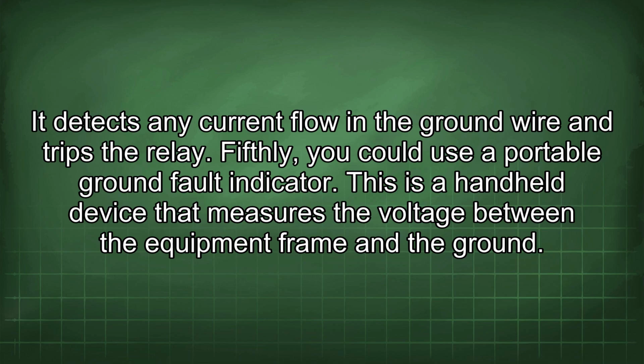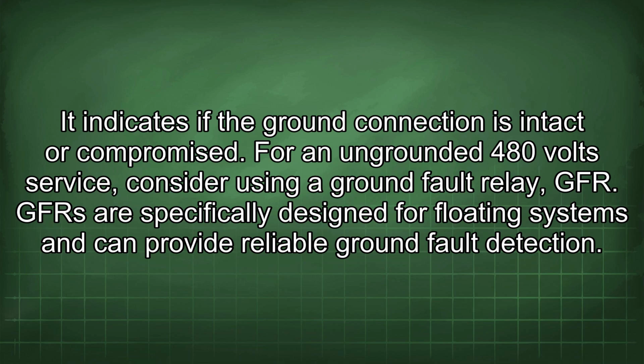Fifthly, you could use a portable ground fault indicator. This is a handheld device that measures the voltage between the equipment frame and the ground. It indicates if the ground connection is intact or compromised. For an ungrounded 480-volt service, consider using a ground fault relay, GFR. GFRs are specifically designed for floating systems and can provide reliable ground fault detection.